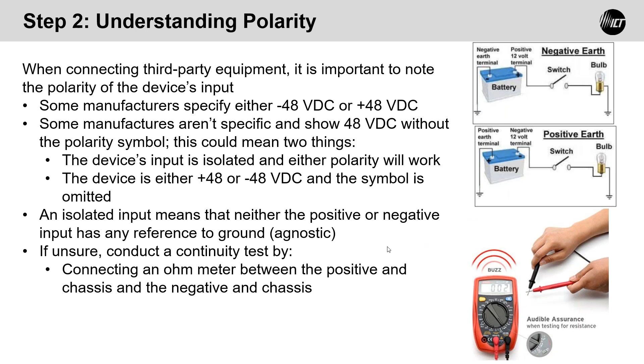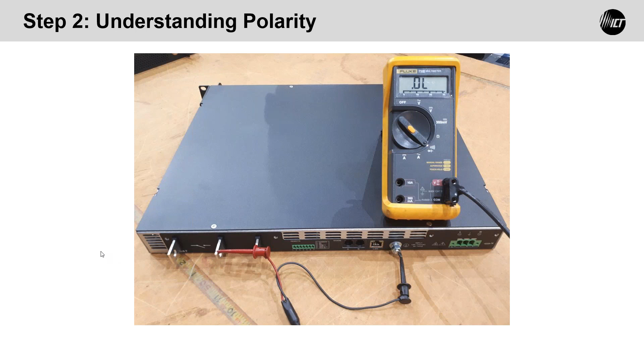This is an example of what that would look like. We've got one probe connected to the ground lug on this particular device, and the other could alternatively be connected to the plus and minus side of the output of the device. If you don't hear any buzzing, the device is floating or agnostic. If one of them buzzes, that gives you an indication as to whether it's positive voltage negative ground or negative voltage positive ground.